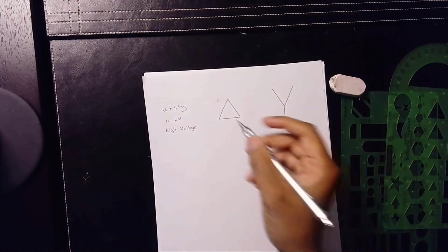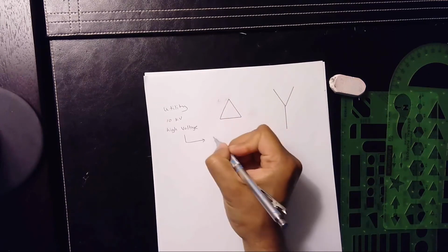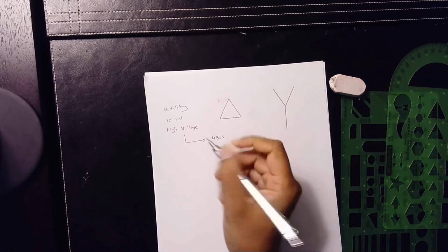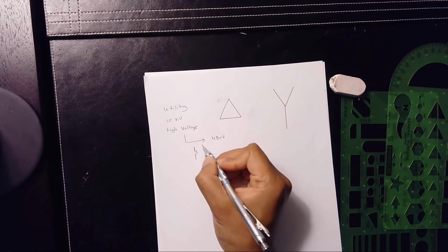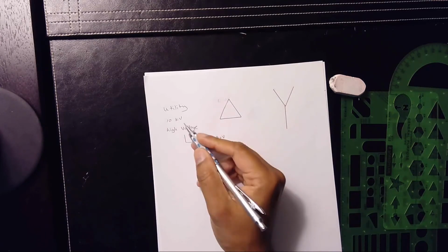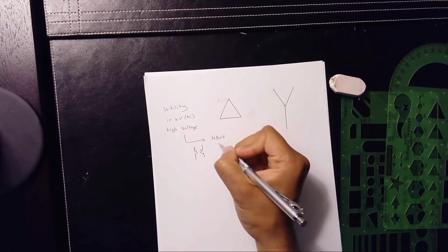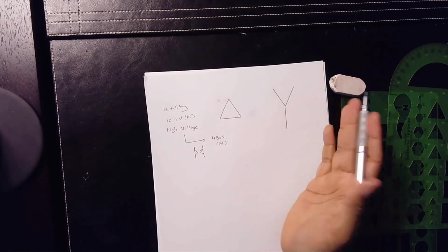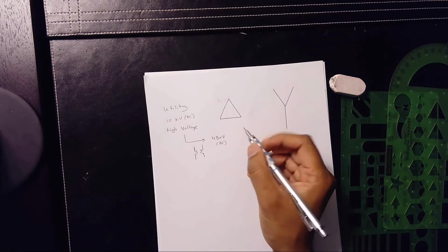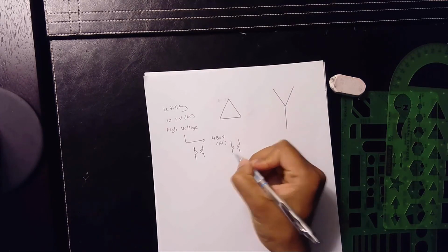So we would say, okay, so it's coming in from here to here is 480. And this is probably a transformer drop. Okay? And this is AC, it's all AC, okay? Let me write this out, AC. Then at 480, there's a delta usually, right? And this becomes a transformer drop again to 208.